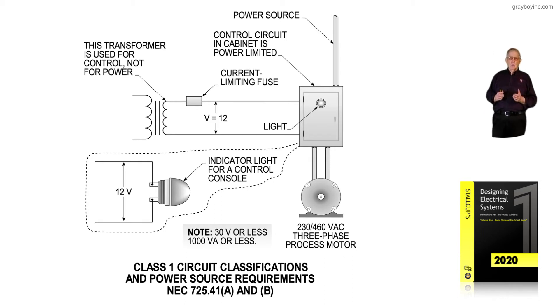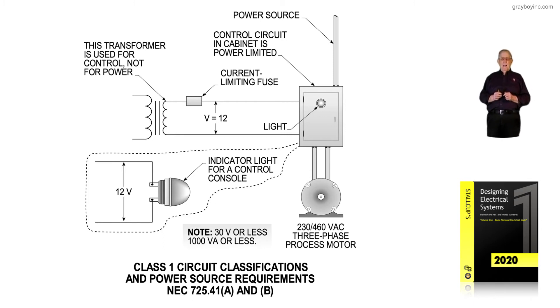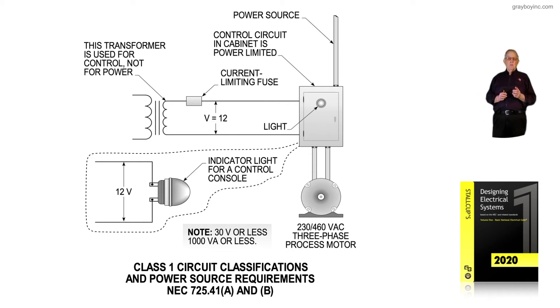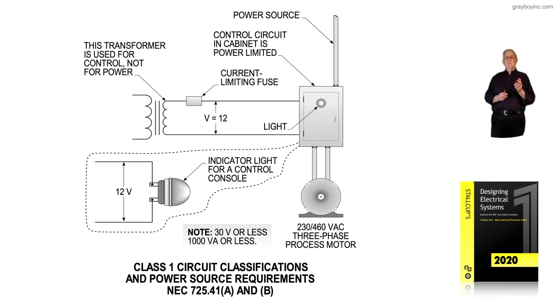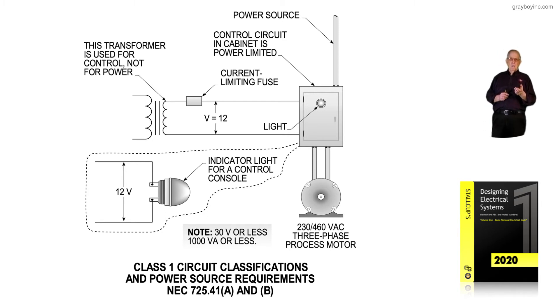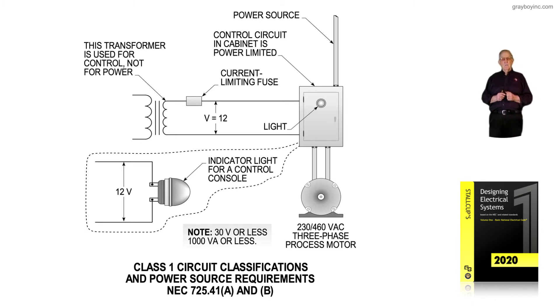In this illustration, we're looking at 30 volts or less and 1,000 volt-amps or less. We have a three-phase power supply to a process motor, and a control transformer usually mounted in a combination starter with a stop and start button on the cover. The transformer taps off 480 volts coming into the contactor and steps that voltage down to a power-limited circuit of 12 volts.